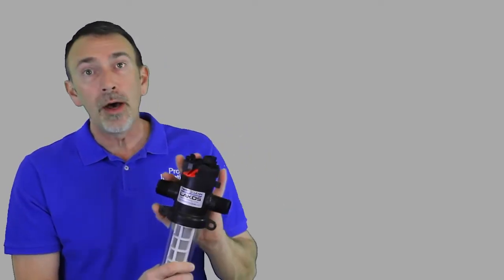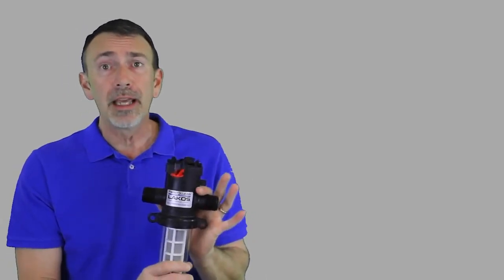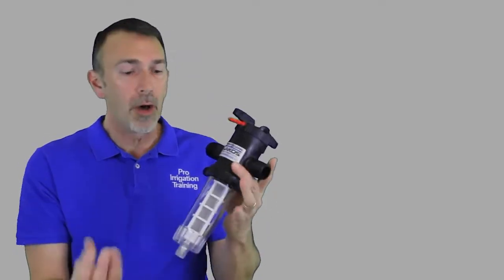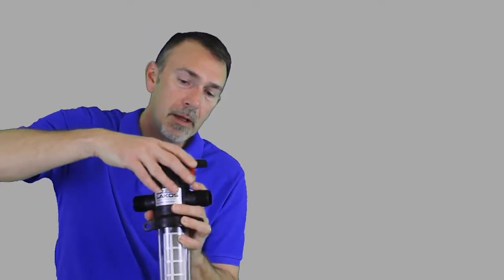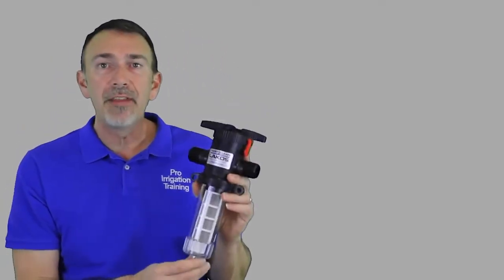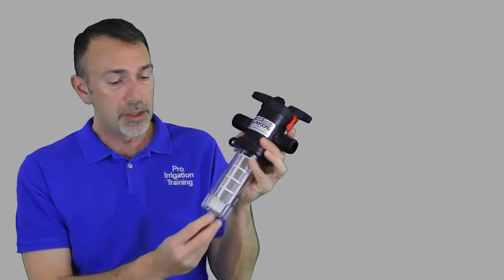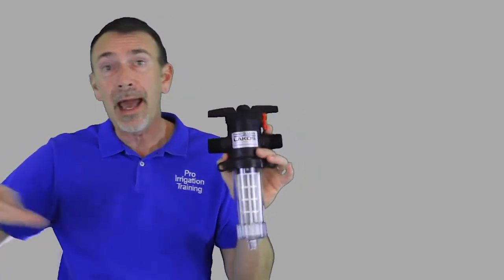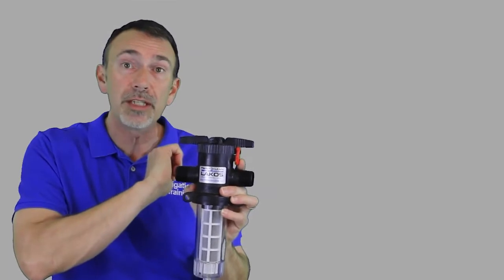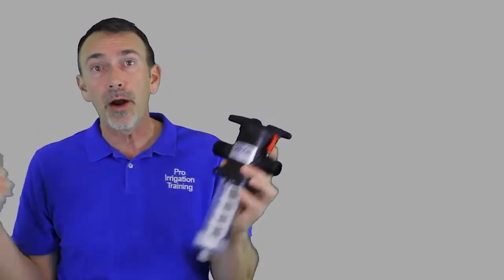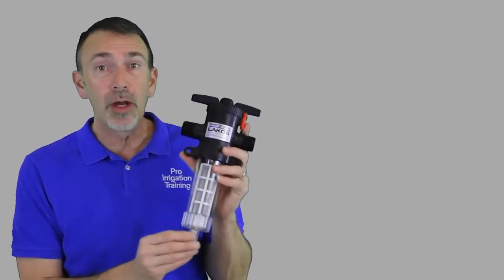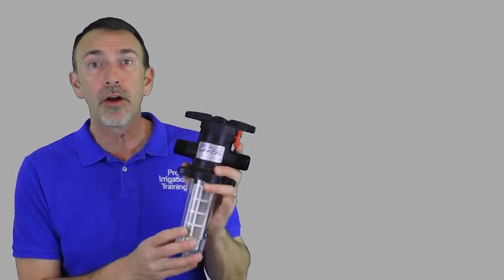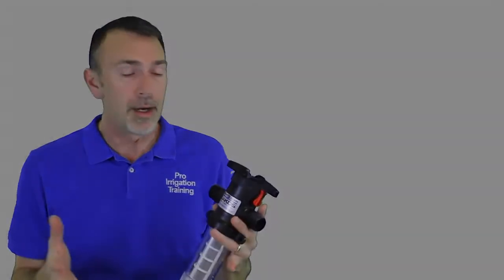The ones that I know of on lake systems, they clog up pretty frequently and need to be cleaned at least two, if not three times a year, just from the way that lakes work as far as the organic particles that settle to the bottom. And if you've got a particularly strong pump, it can pull stuff up off the bottom and into the system. So let's close this back here. And one of the things that you can do in the places that I have these installed underneath the house, then you'll want to put a fitting on here and run some flexible tubing outside of the foundation so that when you blow this out and clear all the stuff out of it, it goes somewhere other than underneath the house.